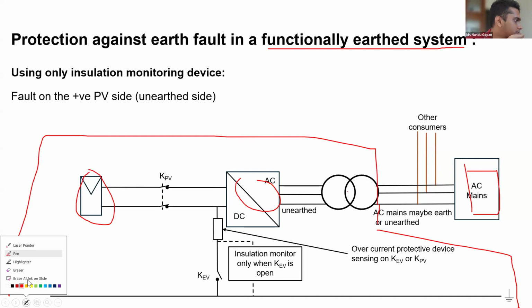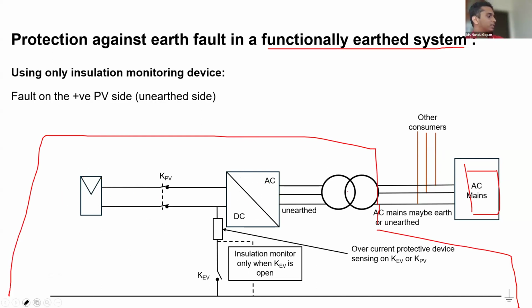So in this, what happens is, in case of a fault on the positive side, functional earthing is done on the negative conductor. So if there is a fault on the positive side, the current will be coming here. This is how the current travels. There will be an overcurrent protective device over here, and depending on how many amps are coming, it will trip. After tripping, it will sense on this one or this one. Now, after this trips, this will become an IT source with the first fault.